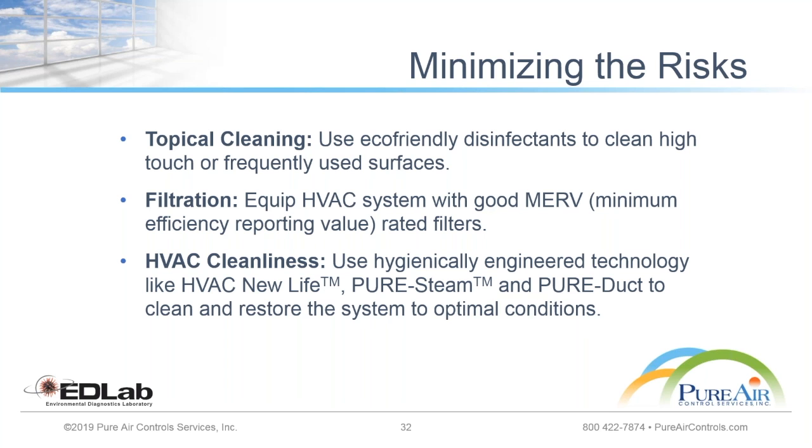We keep repeating that HVAC systems with poor MERV-rated filters are not good. We need to put in a filter rated MERV greater than 8 or so, just to maintain the air quality by filtering out foreign bodies, debris and allergens, and not let them go into the building air conveyance system.